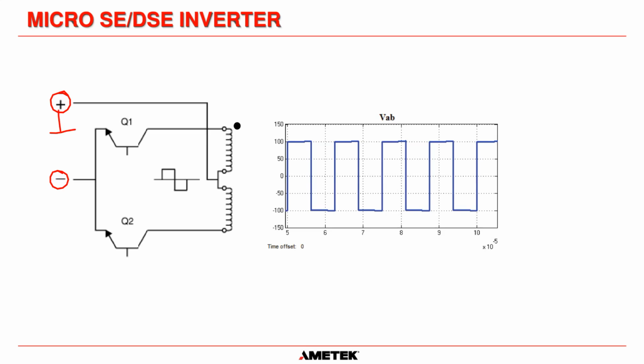So this is always going to be connected to the battery, because the battery is there just in case power fails, and we can still carry on converting DC into AC. Okay, and now we only have two IGBTs for this design of circuit, and we have a center tapped transformer. So if you look carefully here, you can see the positive is connected to the center tap of this transformer. Very important to understand. That doesn't move, so that is always going to be positive. And you can see negative is connected to the emitter for both of these IGBTs.